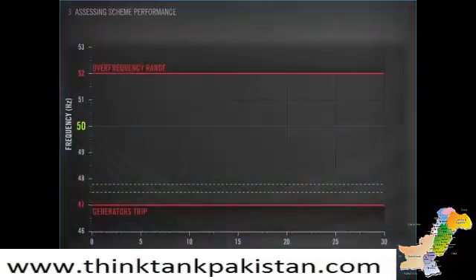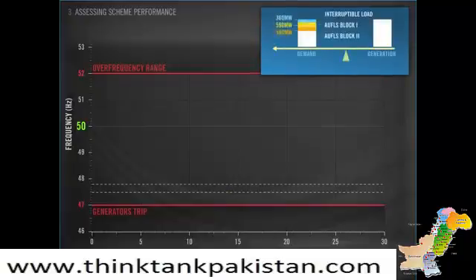Let's return to the graph, which shows frequency on the vertical axis with time on the bottom. Over on the seesaw, we've shown a medium load scenario. You can see interruptible load at 360 megawatts and two AUFLS blocks of 590 megawatts each. This is the amount of load we can control and disconnect from the grid to tackle any size loss in net injection. These will stay fixed throughout the analysis.